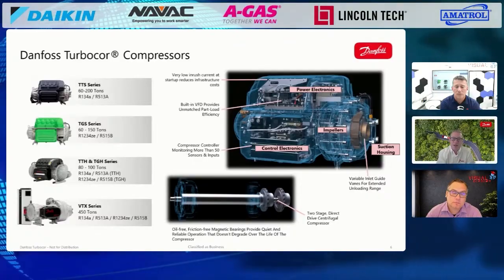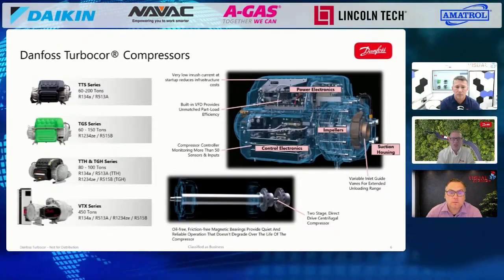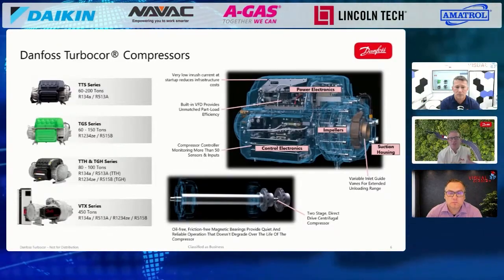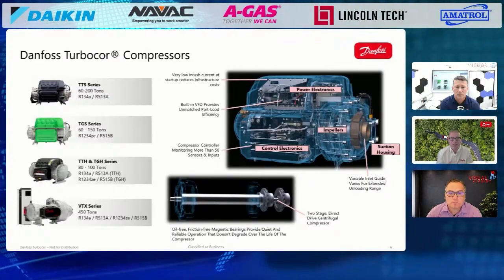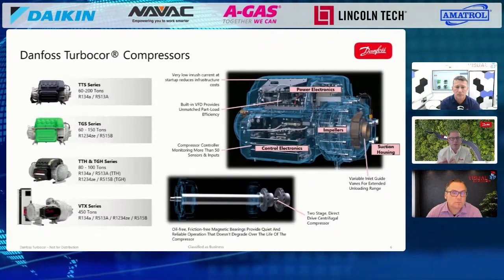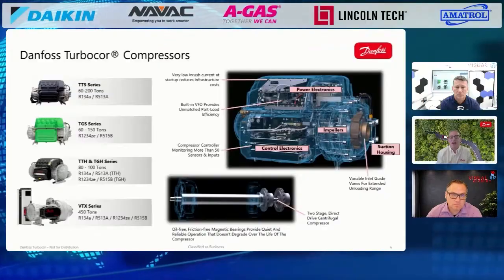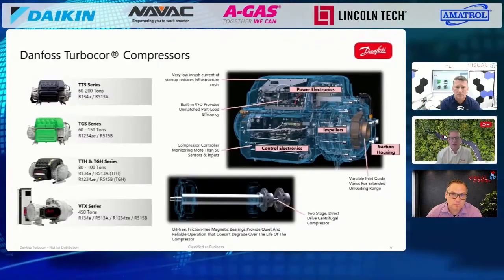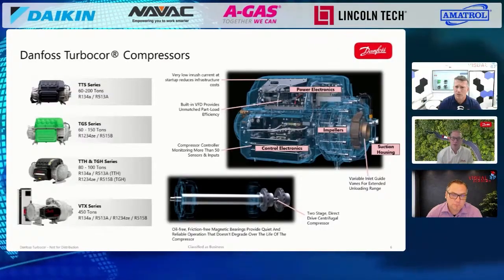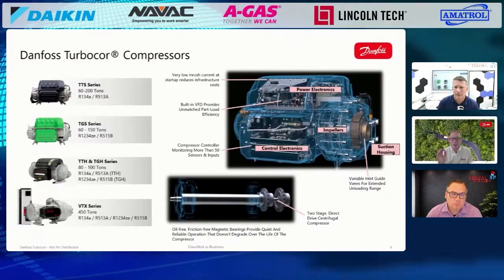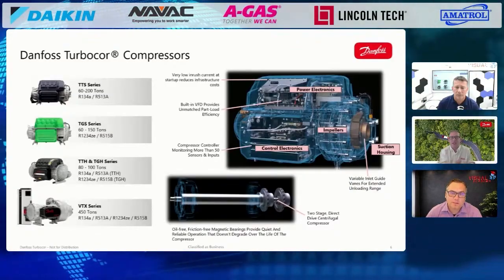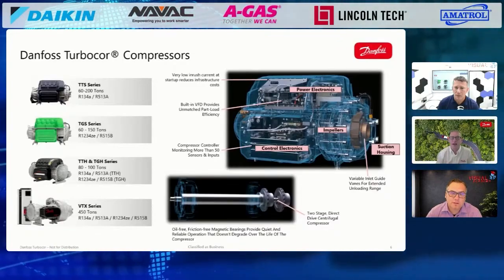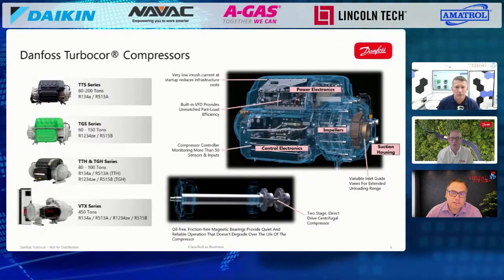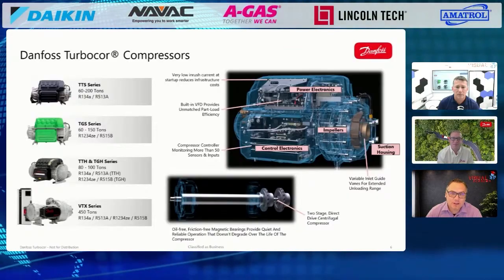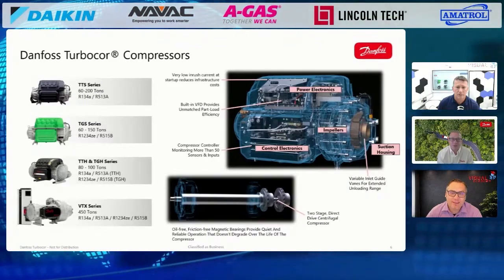And then the TTH and the TGH series are very similar, except for, as you can see on that shaft, the 2 impellers are back to back. With the high lift, we call it, the TTH and TGH, we're going for higher pressure ratios. So we have an impeller on the suction, and then we have an interstage that goes to the backside where we put another impeller to get that higher lift, that higher pressure ratio. So it's basically like a dual stage compressor in a way. Yep, kind of, yeah. Absolutely.